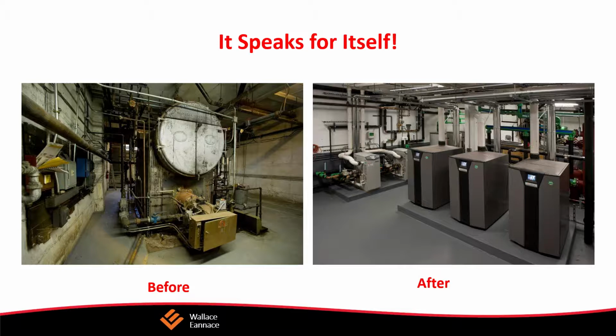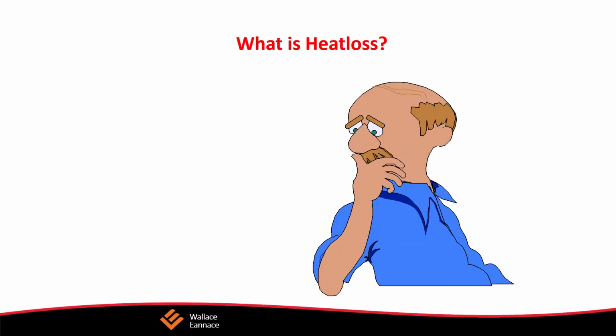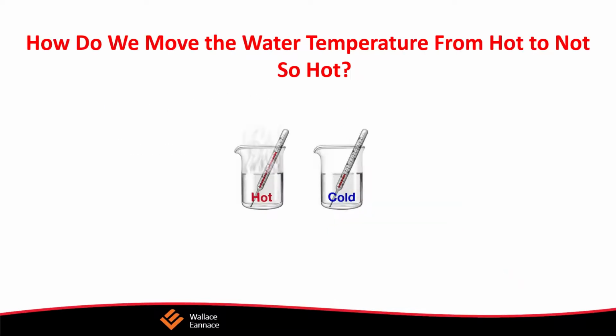Here's a boiler room, and you can see what the situation was before, and here you can see the after. I mean, it's pretty stark and pretty obvious. So when looking to optimize these systems, one of the first questions we have to ask ourselves is, what is the heat loss? But let's talk about what exactly heat loss is. Heat loss is the rate at which heat leaves the building under what conditions, and from that information, how do we size the boilers and how do we size the radiation?